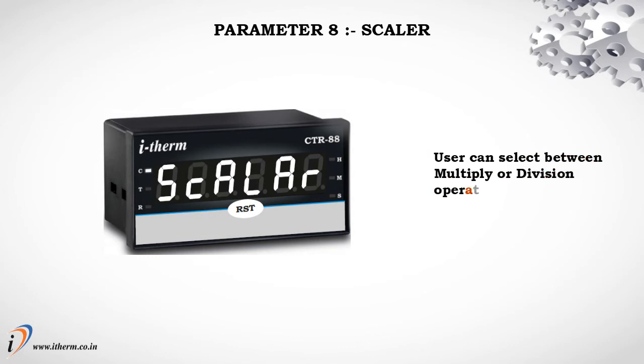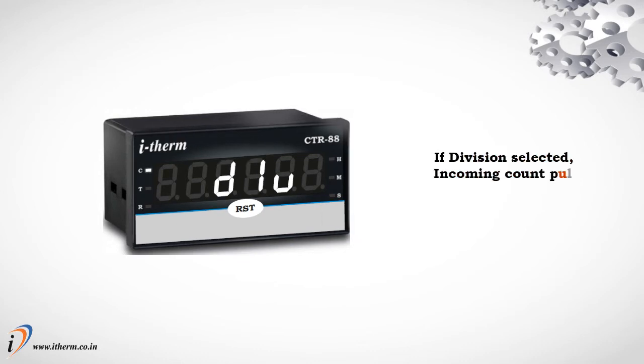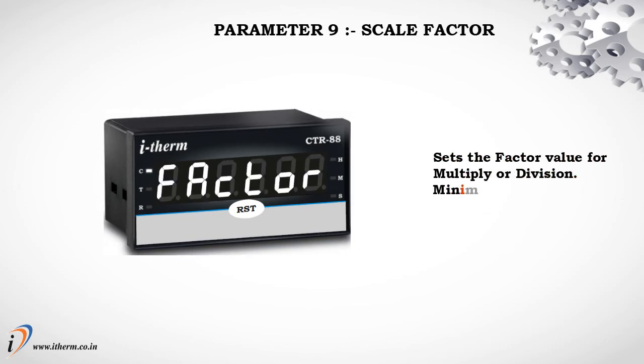Parameter 8: scalar. The user can select between multiply or division operation for the incoming count pulse. If multiply is selected, the incoming count pulse is multiplied by the factor selected by the user. If division is selected, the incoming count pulse is divided by the factor selected by the user. Parameter 9: scale factor. Sets the factor value for multiply or division. Minimum factor value equals 1; maximum factor value equals 99.